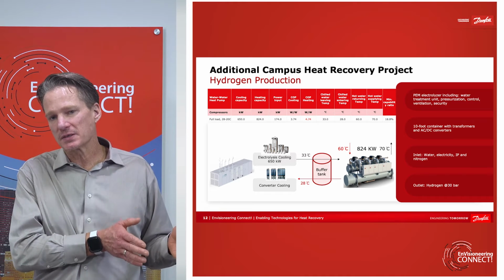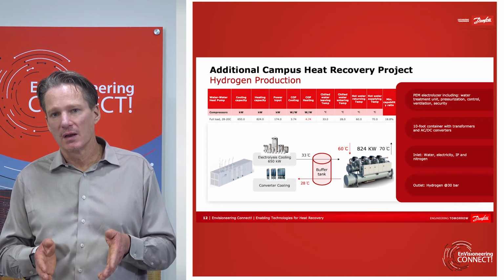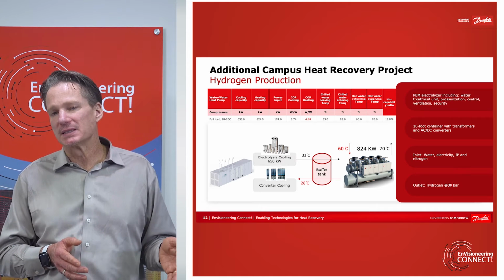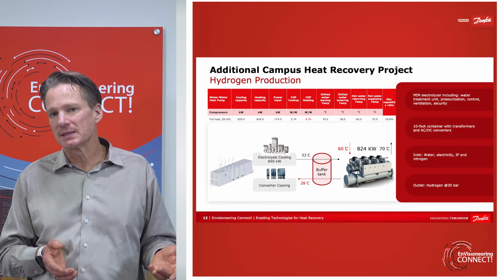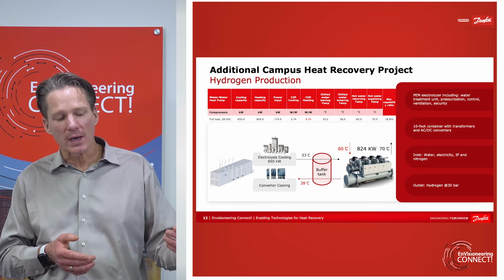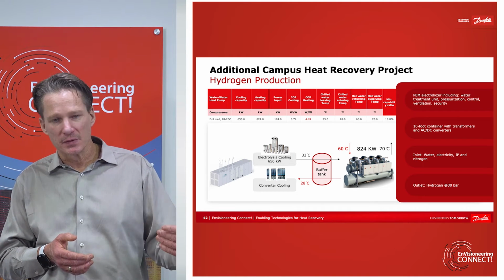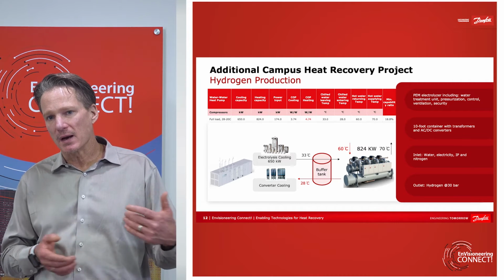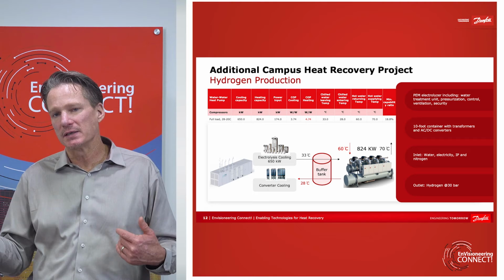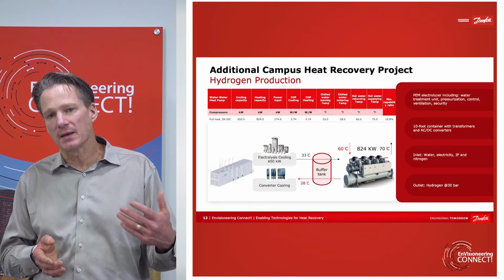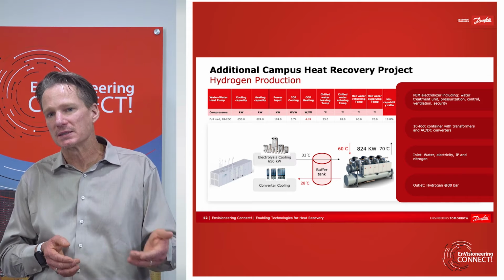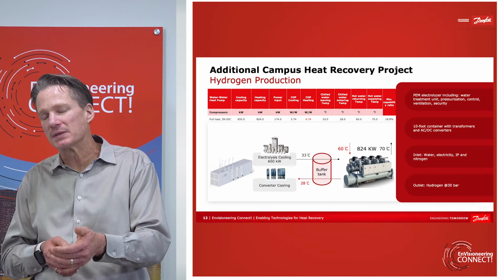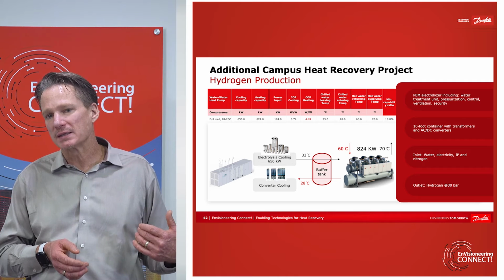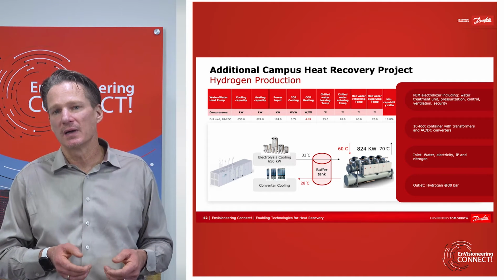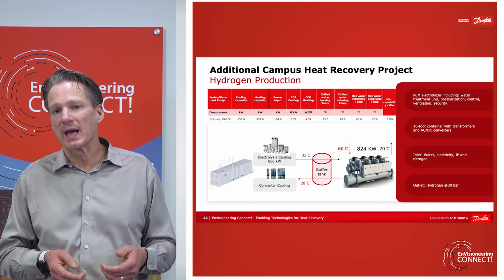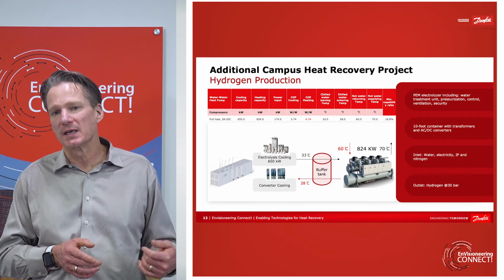Both of those processes, the electrolysis and then the fuel cell, are not extremely efficient. But that inefficiency is, luckily for us, also heat. So in that same application, if they're running this backup power system that in the future is based on hydrogen, and then operating the water-to-water heat pump to provide both cooling and heating to the district heating grid, then you can integrate in as well the heat recovery from this electrolysis process and the fuel cell power generation that's now powering the equipment for the data center to recover additional heat to the district heating system. Roughly double that of what's possible from the cooling system for the data center itself.